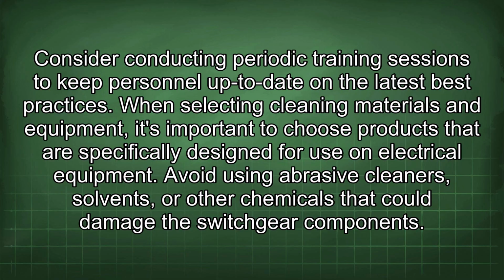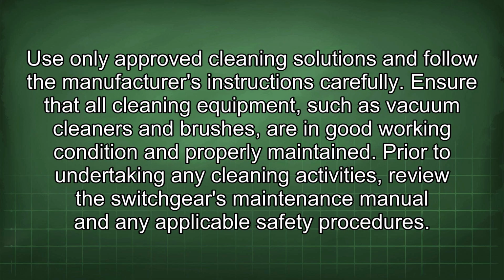When selecting cleaning materials and equipment, it's important to choose products that are specifically designed for use on electrical equipment. Avoid using abrasive cleaners, solvents, or other chemicals that could damage the switchgear components. Use only approved cleaning solutions and follow the manufacturer's instructions carefully. Ensure that all cleaning equipment, such as vacuum cleaners and brushes, are in good working condition and properly maintained.